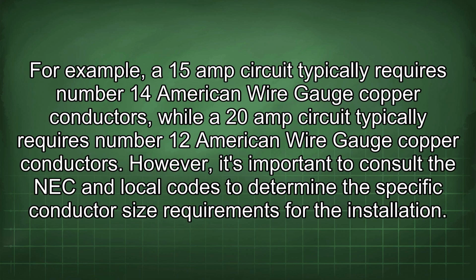For example, a 15 amp circuit typically requires number 14 American wire gauge copper conductors, while a 20 amp circuit typically requires number 12 American wire gauge copper conductors. However, it's important to consult the NEC and local codes to determine the specific conductor size requirements for the installation.